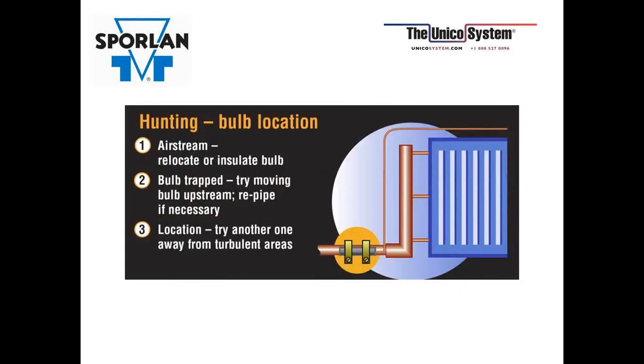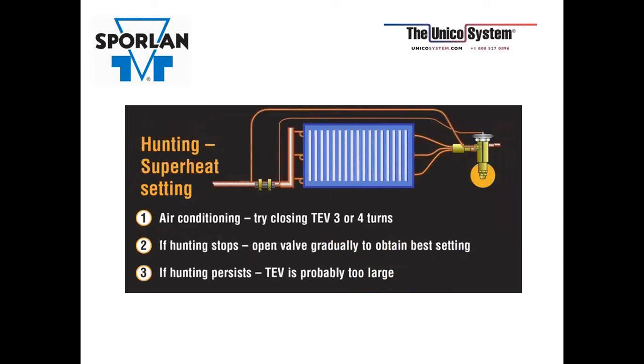And I'd start off with bulb location. If the bulb is located in the airstream, you need to either relocate it or insulate the bulb so it's not picking up ambient temperature, it's only picking up the suction line. Make sure it's not trapped. If so, repipe if you need to. And then the location, if it's somewhere near an elbow or some other kind of turbulent area, move it away from that area. If you're hunting and it might be a superheat setting, in air conditioning, try closing the valve 3 or 4 turns. If the hunting stops, then open the valve gradually and try to find that best setting. But if it still hunts, then it's probably an indication that the valve is too big to begin with.